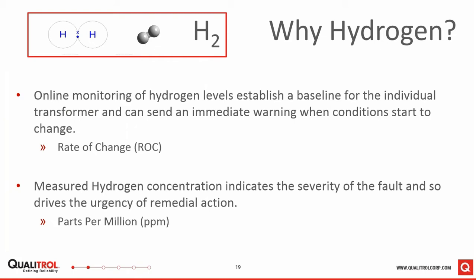Again, why hydrogen? Two reasons are shown here. If we continuously monitor hydrogen, we can see not just the concentration right now, but the changing concentration with time, something that you can't see with offline testing. Therefore, we know the rate of change of hydrogen, and the rate of change can be related to accelerated changing conditions within the transformer. If you have a fault and it's getting worse really, really slowly, you may not take any action. If it's getting worse really, really quickly, as indicated by the rate of change of the gas concentration, that's a different story.